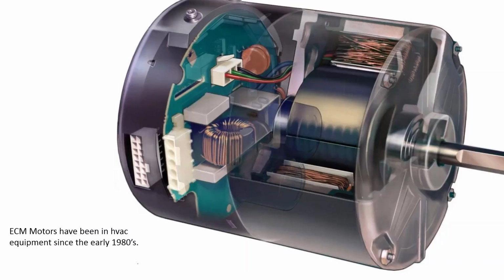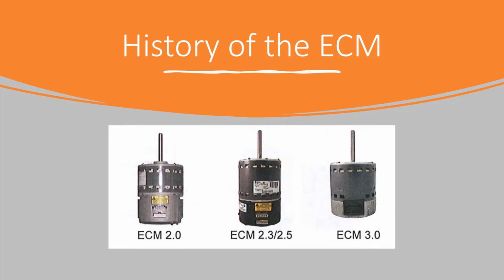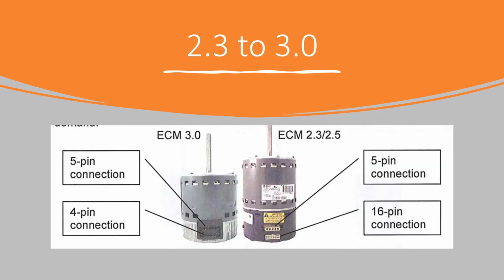ECM motors have been in HVAC equipment since the early 1980s. The ECM motor history began with the 2.0 motor and has progressed to the 2.3, 2.5, and to the current 3.0 and other current models that are available. The 2.3, 2.5 motor had a 5-pin high voltage connection with a 16-pin communication connection. The ECM 3.0 still has the 5-pin connection for high voltage, but now has a 4-pin communication module.